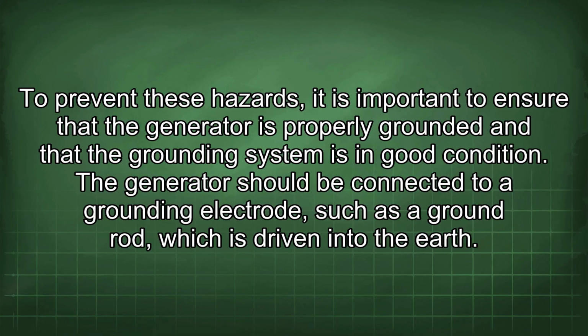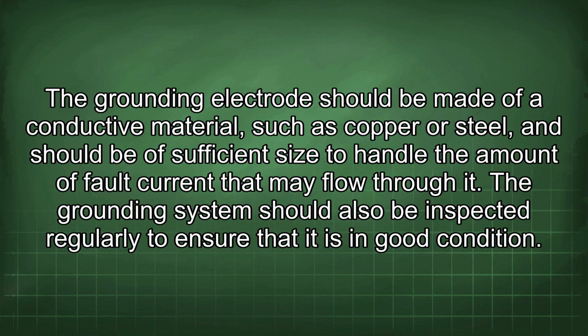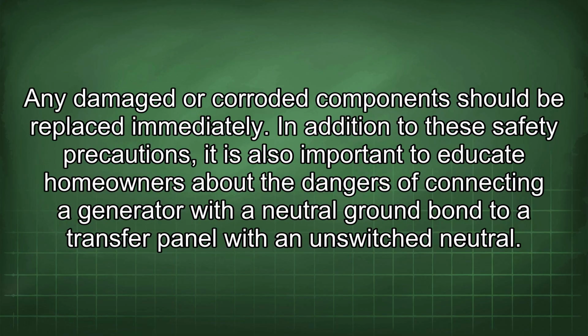The generator should be connected to a grounding electrode, such as a ground rod, which is driven into the earth. The grounding electrode should be made of a conductive material, such as copper or steel, and should be of sufficient size to handle the amount of fault current that may flow through it. The grounding system should also be inspected regularly to ensure that it is in good condition. Any damaged or corroded component should be replaced immediately.